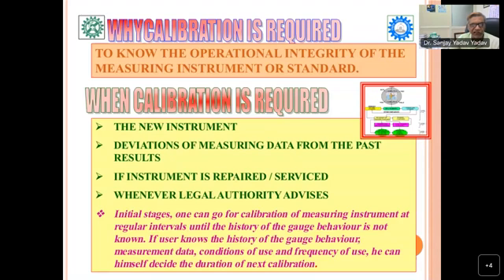When is calibration required? Any new instrument requires calibration. Deviation of measuring data from the past: if you observe your data is deviating from previous data, then you have to check and recalibrate the instrument. If the instrument is repaired, serviced, or adjusted, you have to get it calibrated. And the fourth one, whenever a legal authority advises, by legal authority I mean your accreditation authority also, your legal metrology department also, if any legal authority advises you to go for calibration, you have to go for the calibration.